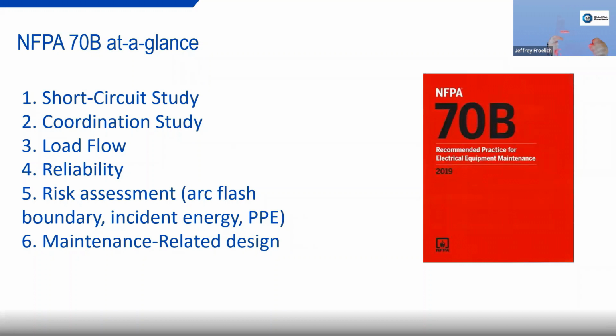Yes, NFPA 70B, unfortunately, with the backdrop it doesn't show, but it is a very illustrious and lengthy document. You can go to Annex L, which is the maintenance intervals. It'll provide you with an initial guideline for inspecting, testing, and maintenance of your electrical equipment. It'll break it down into specific items, components, tasks, functions, and frequency intervals of inspection. This could range from things like bus and cable, based on the voltage and the type, switchgear, relays, battery, rotating machinery, generators, AC or DC motors, transformers. There's a whole host of assets that need to be checked, inspected, and tested by qualified professionals.